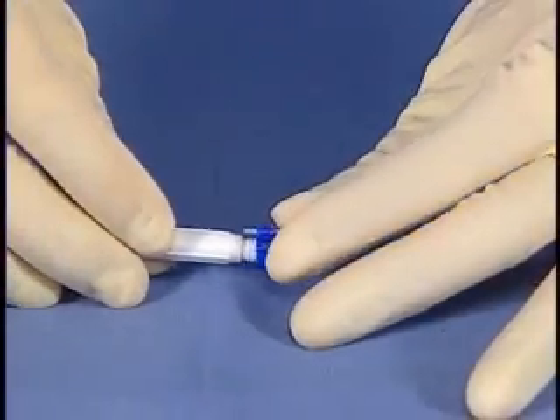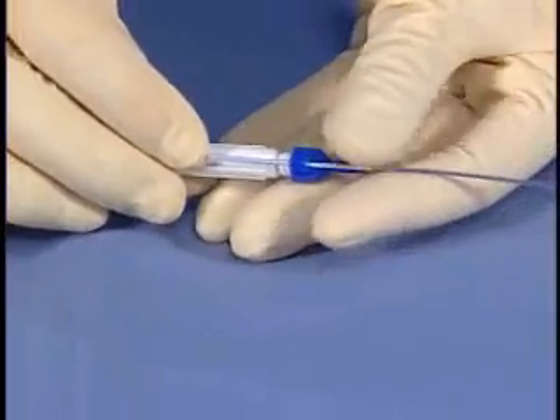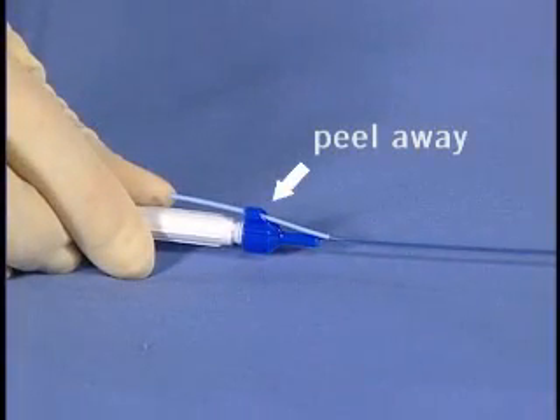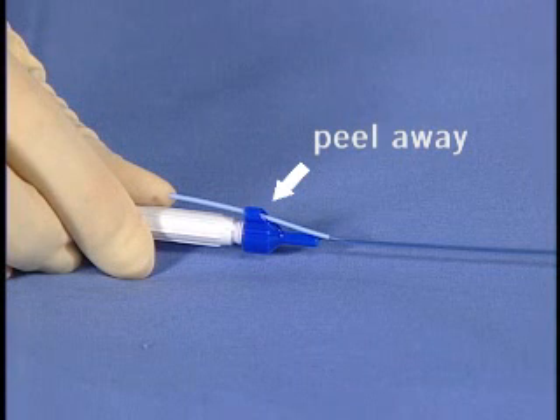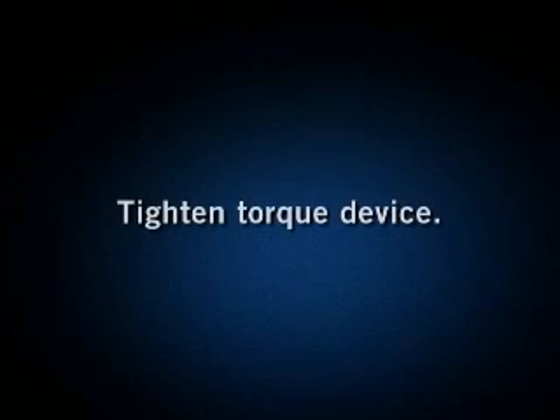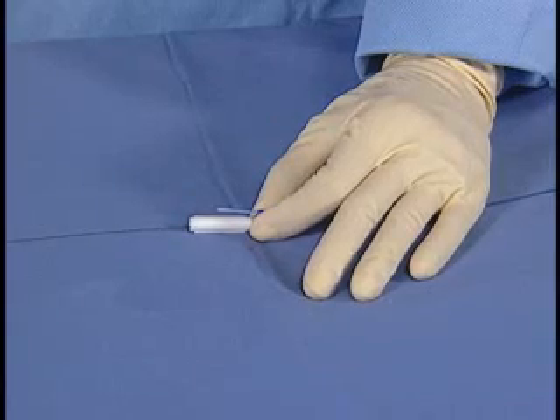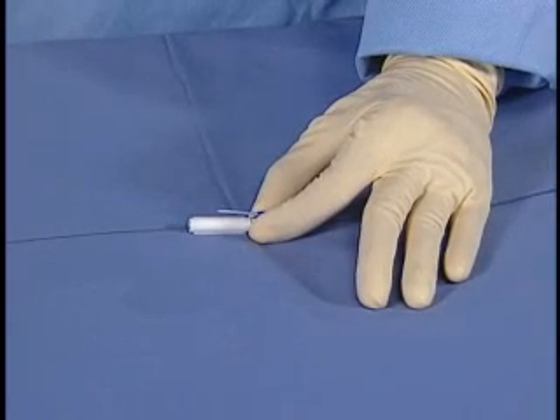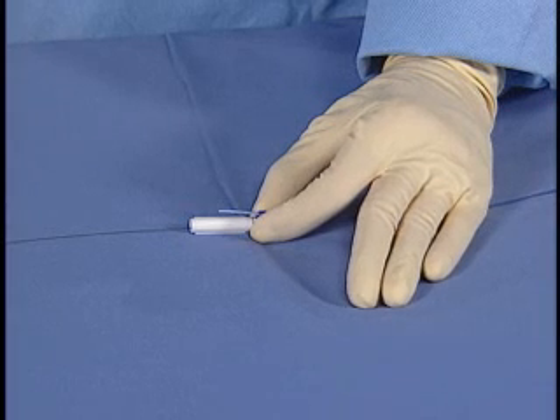Thread the light blue polymer through the side hole of the peel-away adapter on the torque device until the tip of the collet tube is at the position where the delivery sheath splits off from the guide wire. Tighten down the torque device firmly onto the wire. Remove all slack from the delivery system and stabilize the torque device with one hand.